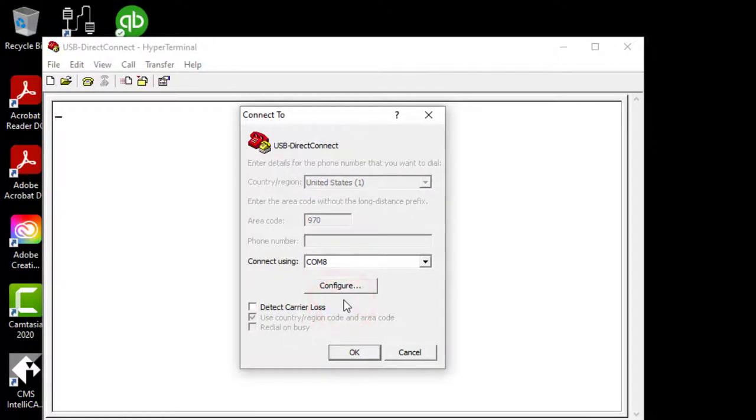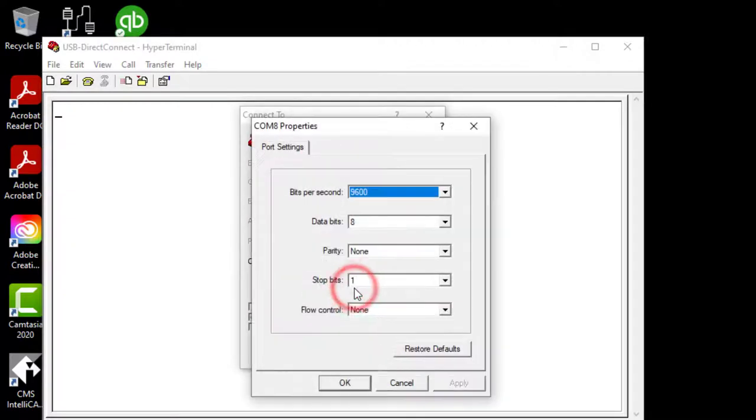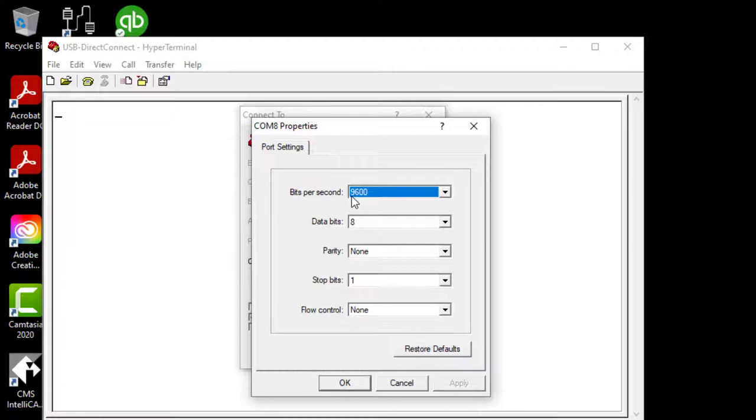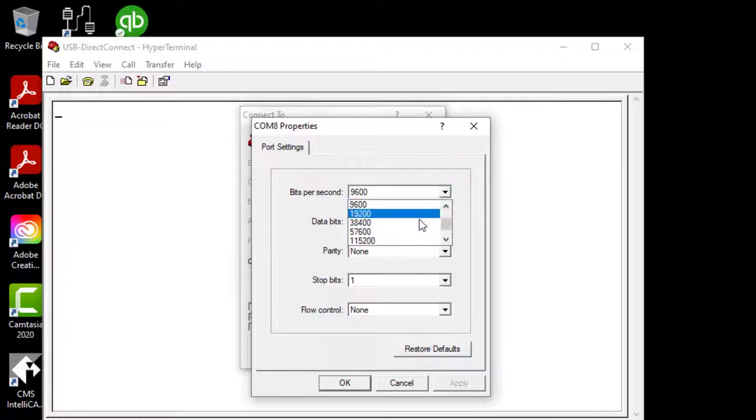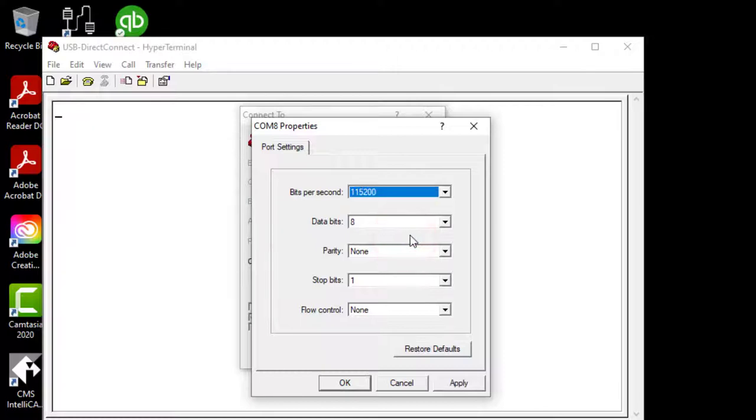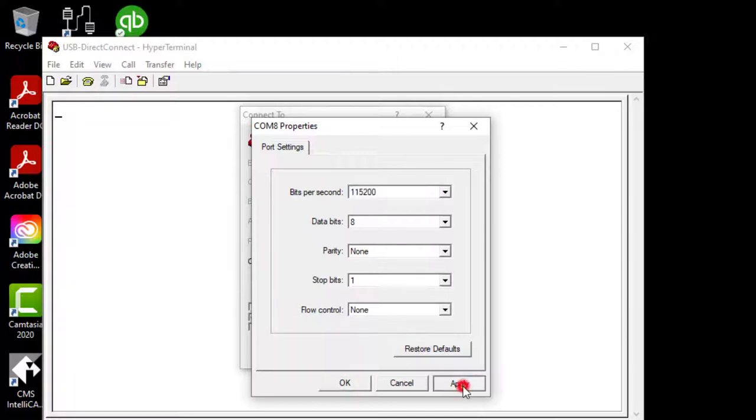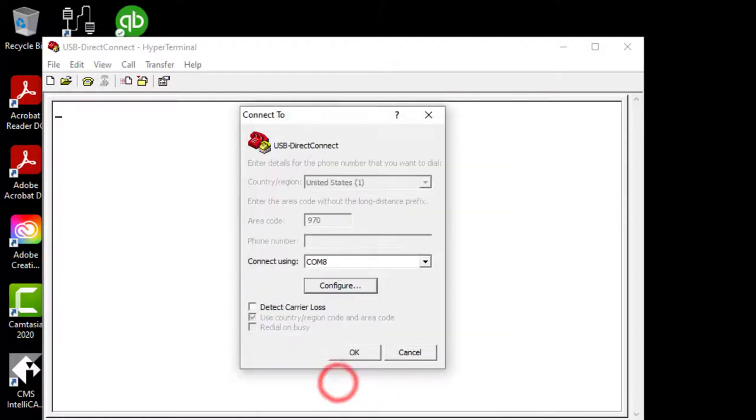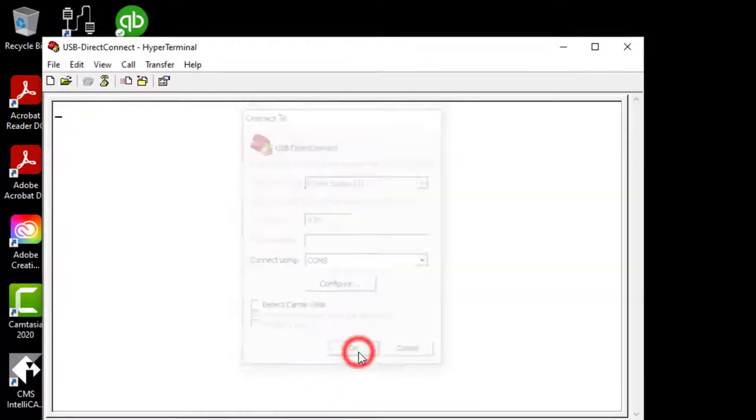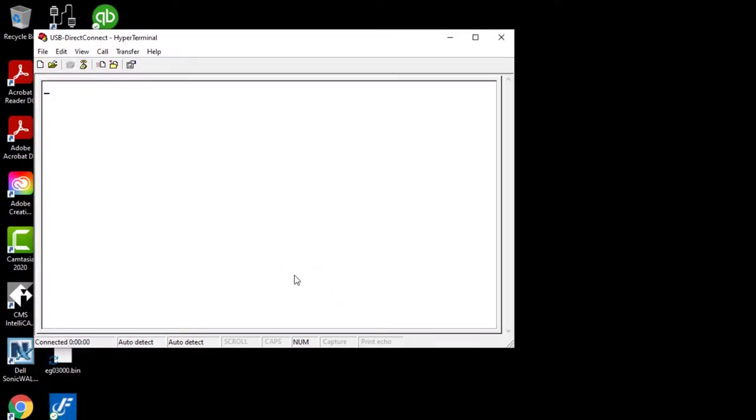Next, we have to configure it because it does not use the standard settings. Here we have our bits per second or better known as our baud rate. Here you want to change this to 115,200. Eight data bits is correct. Parity set to none. Stop bits set to one. Flow control set to none. Click on apply. Click on OK. Click on OK. Now that we have all that information in place.